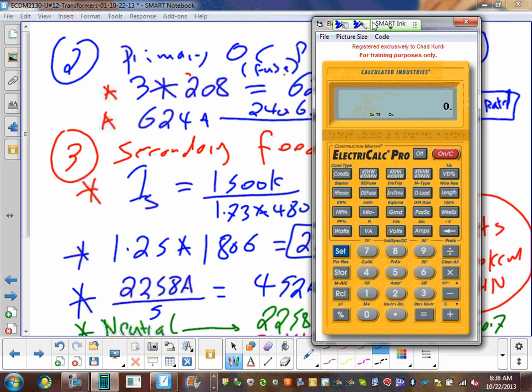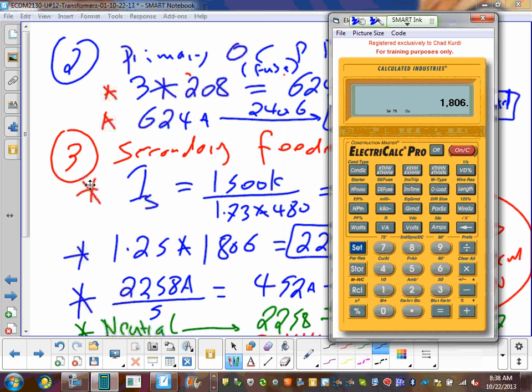Here's 1800. I mean, these are secondary conductors. Okay, so type clear, go clear, will ya? Hit clear a couple of times. Then type 1806. This is how many amps you have for this transformer in the secondary, right? And then since I'm going to multiply it by 1.25, type set and wire size.